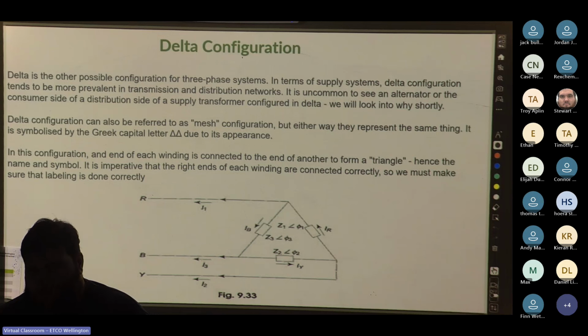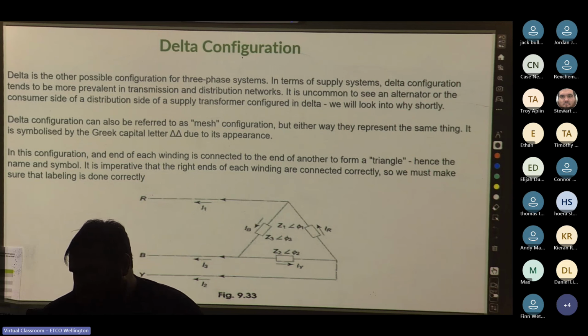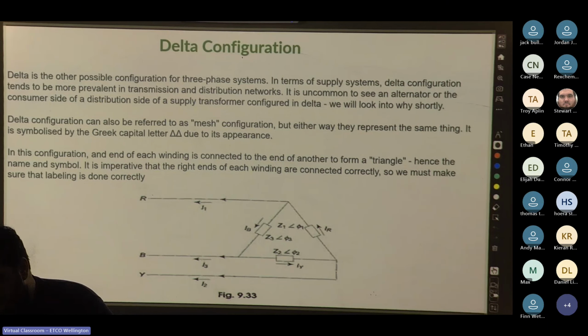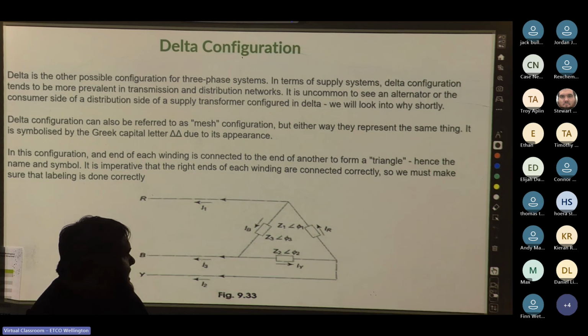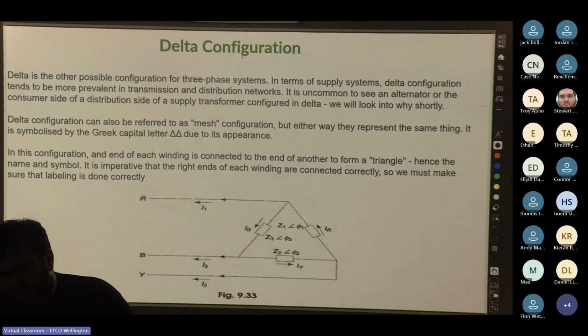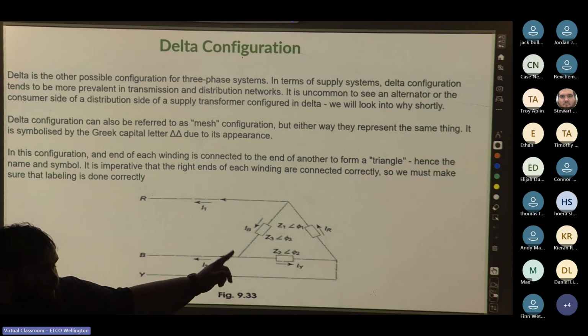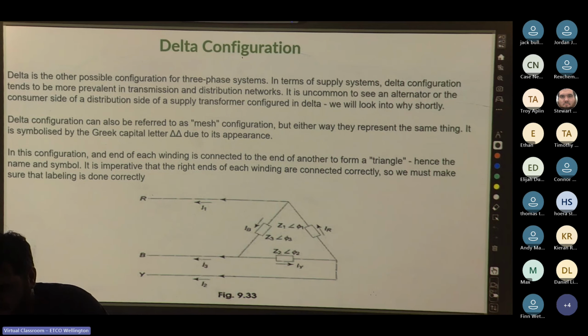Cool. So delta, which is what you can see on the screen. We call it delta because of the Greek letter, which makes it look like a triangle. In the delta connection, the three-phase windings are joined end to end, end to start, forming a closed triangle loop. The triangle shape in the diagram is why we call it delta. So imagine the three separate single-phase windings. Instead of connecting each one to a neutral point, like in star, you connect each end of the winding to the start of the next all the way around, creating a closed circuit for all three coils, almost like it's connected in series. So the three conductors, L1, 2, and 3, are taken from the three junction points.